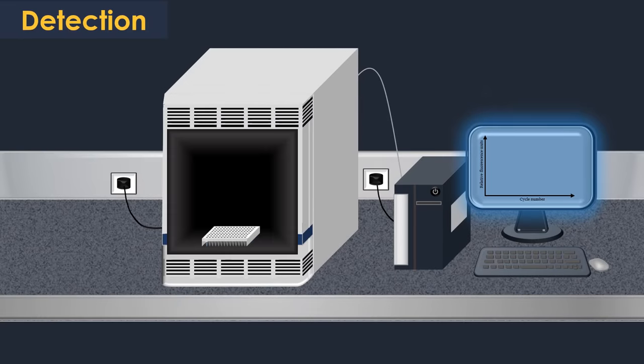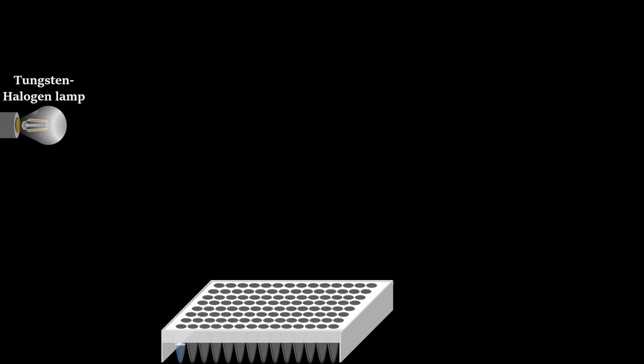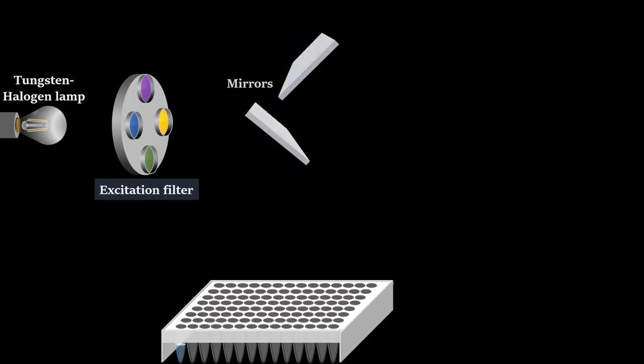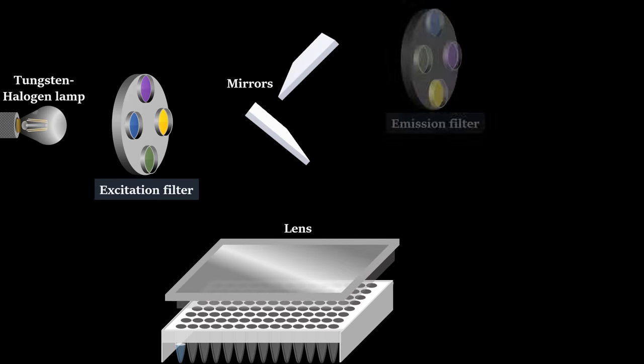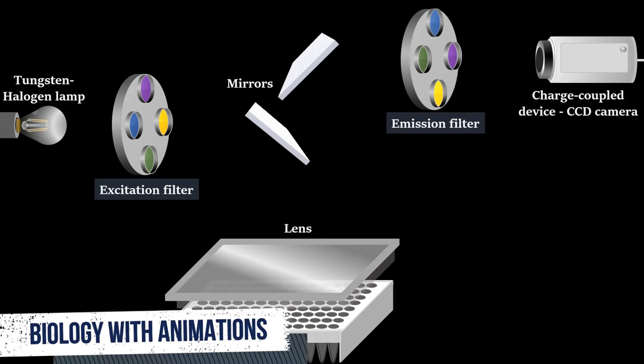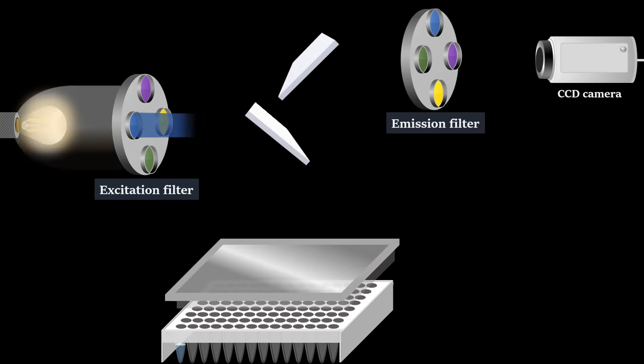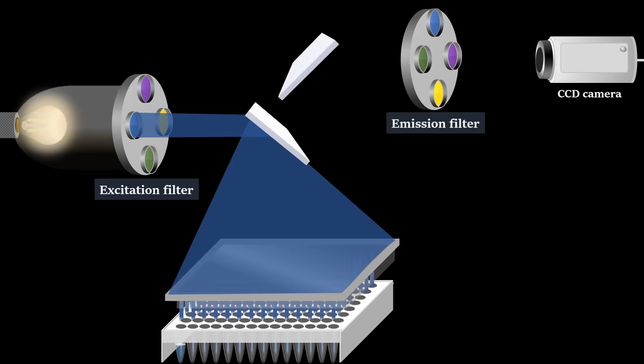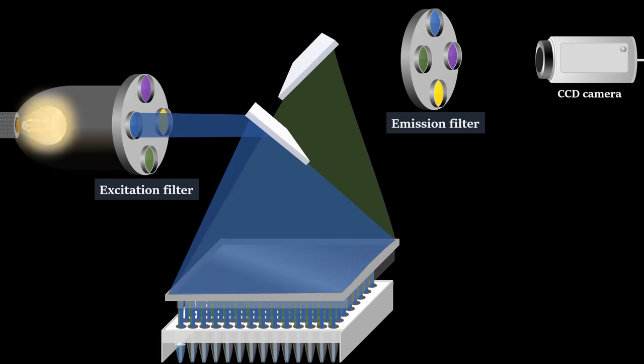For the measurement of the fluorescence signal, a tungsten halogen lamp, an excitation filter, mirrors, lens, an emission filter, and a charge-coupled device CCD camera are used. Filtered light from the lamp is reflected off mirror, passes through a condensing lens, and is focused into the center of each well. Then fluorescent light emitted from the wells reflects off the mirror, passes through an emission filter, and is detected by the CCD camera.